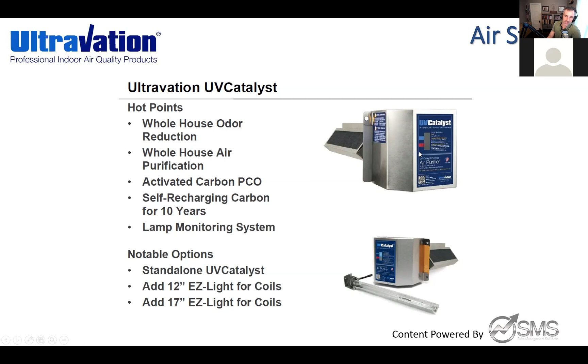And again, with those add-on accessory lamps, I have the ability on this higher end lifetime warranty design that when I take this power head off, everything is mounted in the ductwork, but this power head is outside the ductwork. I just take 2 screws, pop the power head off, and the bulb access is right there. And then I have a secondary bulb inside this power head plug. And I can plug my accessory lamp on and then be able to add on a coil application. So again, per ASHRAE guidelines, we want to see surface area plus airstream. So with a catalyst install, I can go ahead from an easier wiring standpoint and add an extra coil lamp on, just to make sure I'm getting my coil application covered as well. So that's a nice benefit. So I have that installed in my system as well.